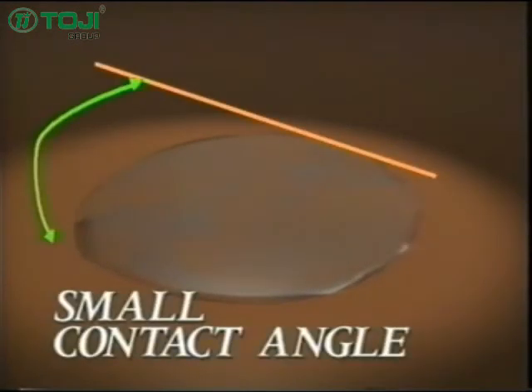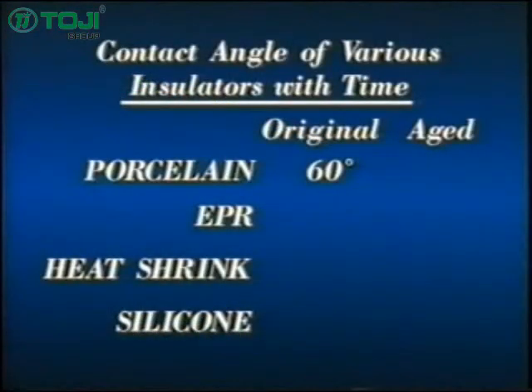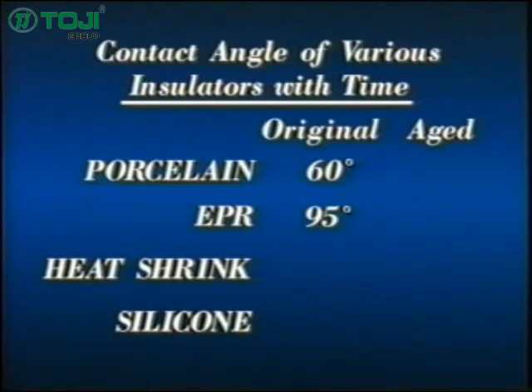In contrast, porcelain, EPR rubber, and heat shrink materials have very hydrophilic surfaces. Water spreads very easily with the most surface coverage and a very small contact angle. Porcelain starts with a contact angle of around 60 degrees. EPR rubber and heat shrink surfaces have a 95-degree angle. Silicone starts out with the best contact angle of around 100 degrees.